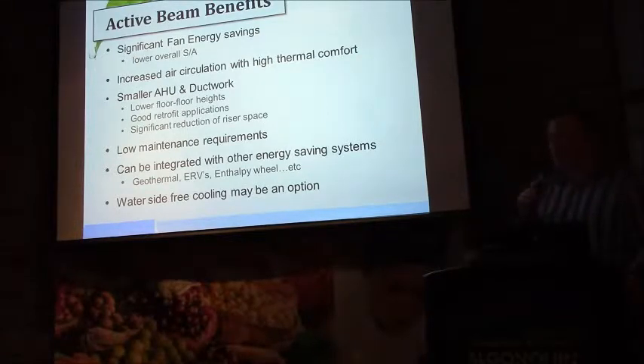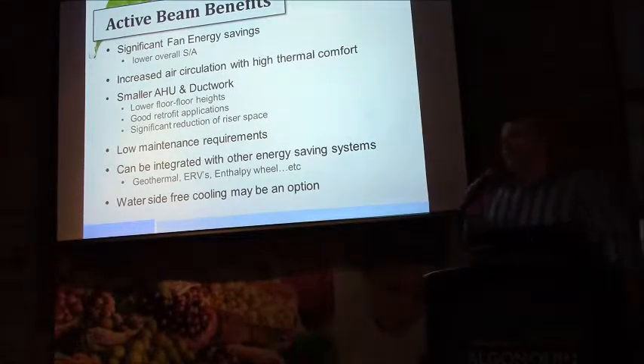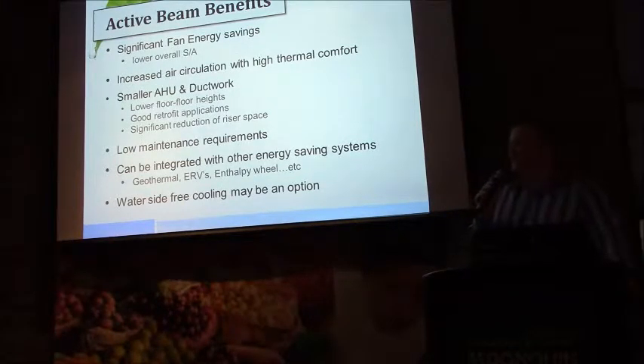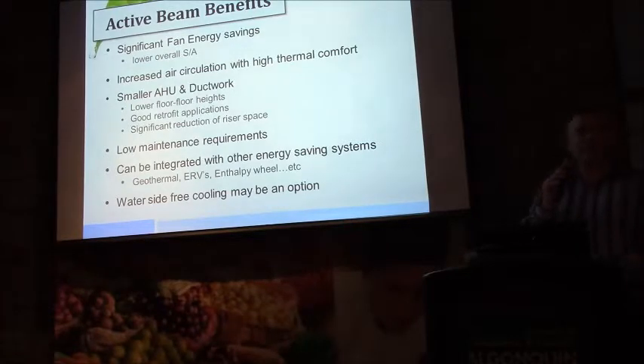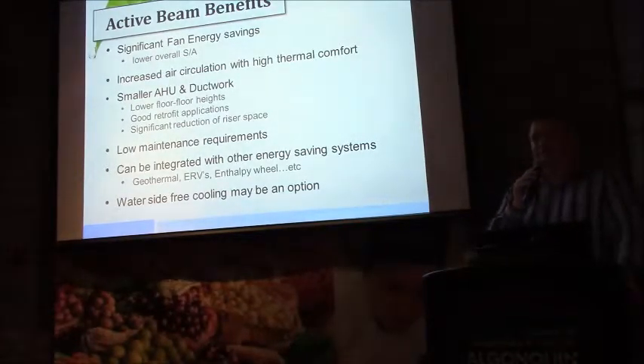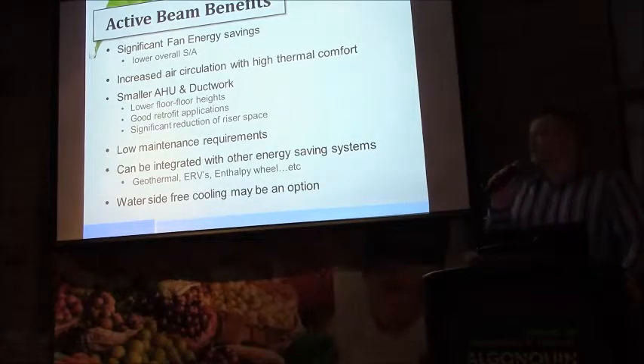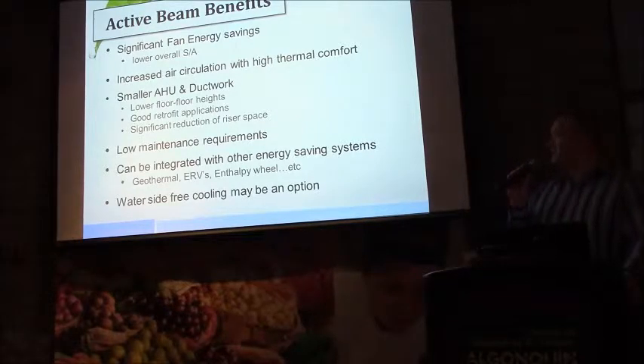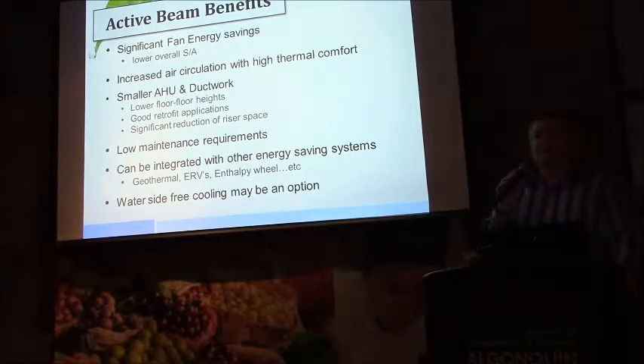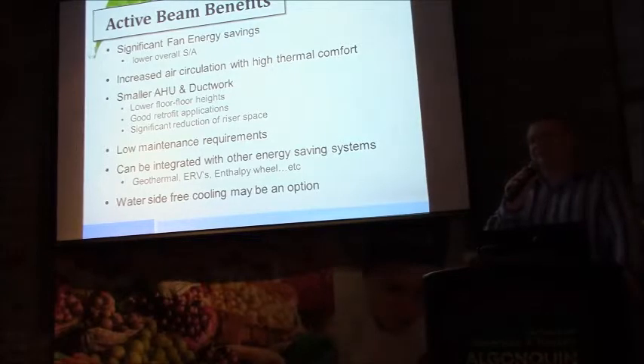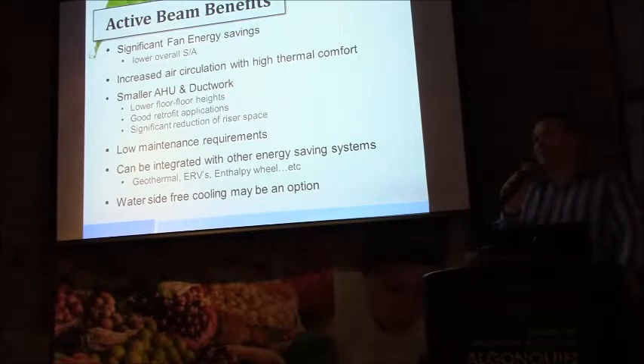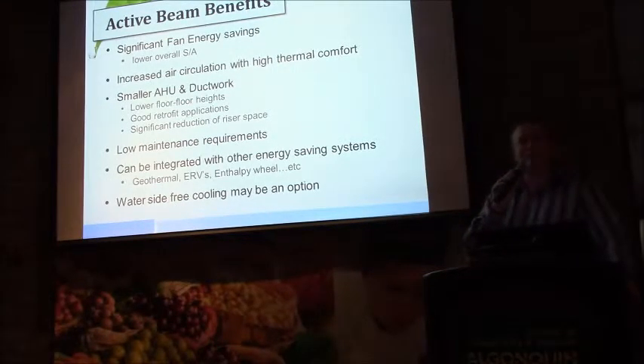Waterside free cooling may be an option. And the only reason I say that in this application or in this slide is it may turn out that waterside free cooling is not attractive. We can't solve it with a simple coil on the outside air handling unit. Maybe we need a fluid cooler. If it's a larger system, a closed circuit fluid cooler can also be attractive. The selection of those becomes quite critical in the fact that the conventional off-the-shelf cooling tower may not be effective at generating the secondary chilled water that we want.